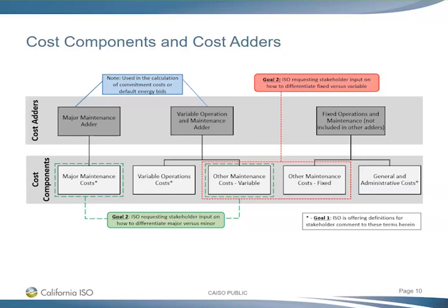And your creep is dollars per hour because the parts have gotten to the point where they're fairly thermally stable, and so it's just a matter of the fact that they're exposed to a high temperature, not a specific high temperature. So I'm curious if this is a move to move maintenance away from dollars per megawatt hour, because technically it's not a load-related generation cost.